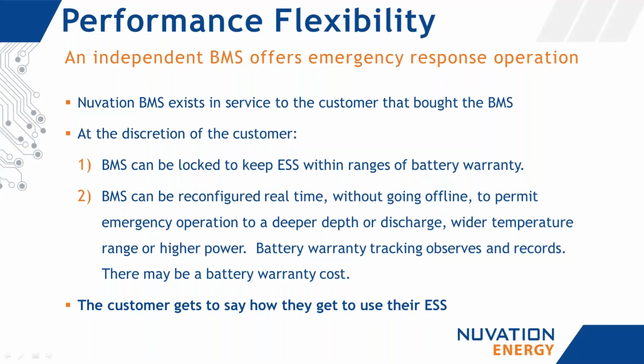My business example: I was talking with the CTO of Italy, who related that they had an issue where there was a frequency regulation event, and the frequency dropped slightly below 60 hertz. They were discharging their Samsung energy storage systems to correct for that, and then the containers hit their 30% state of charge barrier and all went offline, in order to honor the battery warranty.